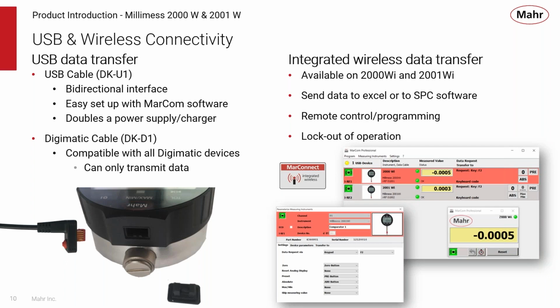And the Digimatic cable, it should be noted, will not work with the MARCOM software. The MARCOM software is a free software from Mahr. It allows computers to communicate with digital Mahr gauges. It will be able to communicate with the Millimess 2000 and 2001, and it'll facilitate the transfer of measuring data from the gauge to Excel or to a third-party SPC software.